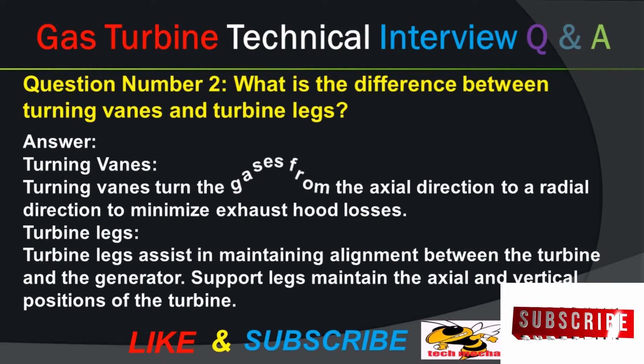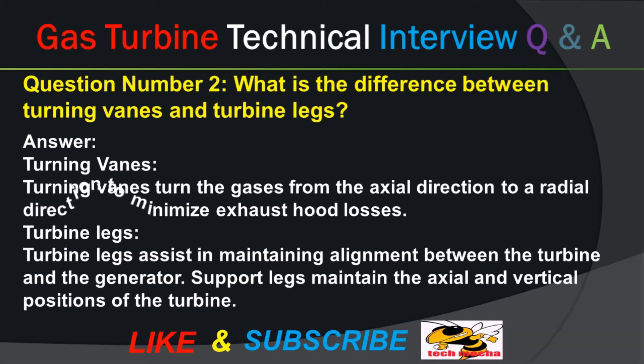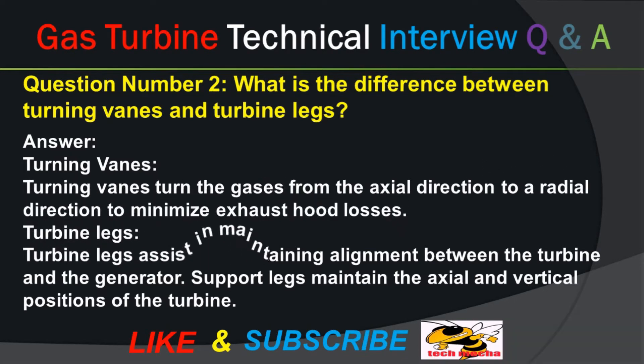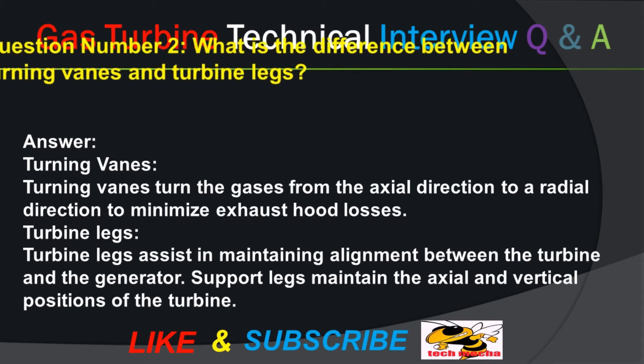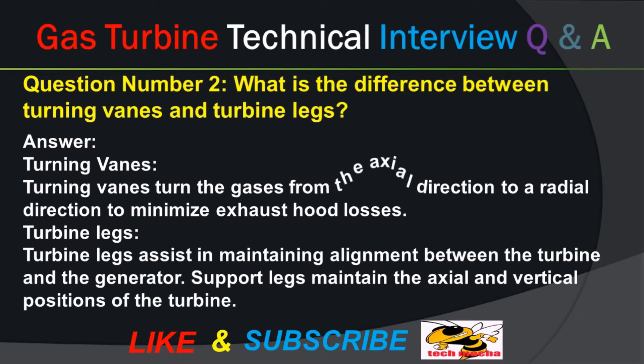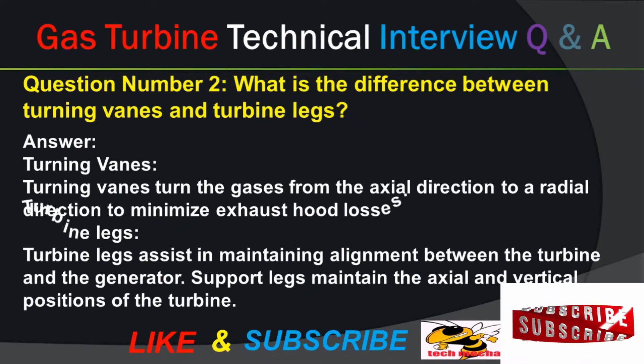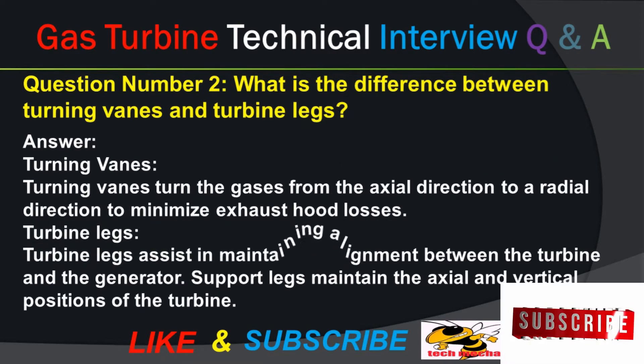Question number two: what is the difference between turning vanes and turbine legs? Answer: turning vanes turn the gases from the axial direction to a radial direction to minimize exhaust hood losses. Turbine legs assist in maintaining alignment between the turbine and the generator; support legs maintain the axial and vertical positions of the turbine.